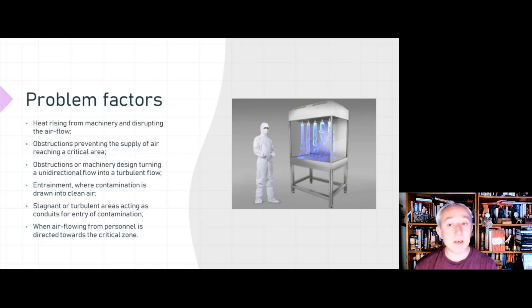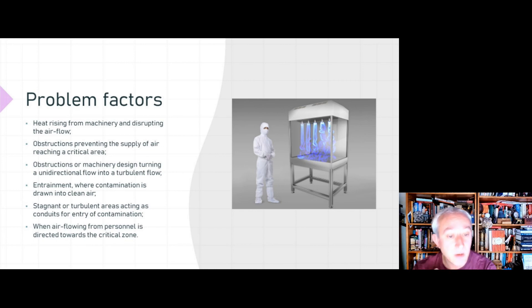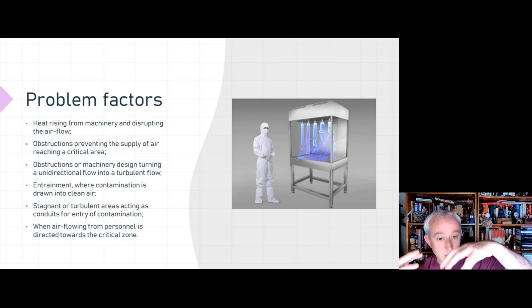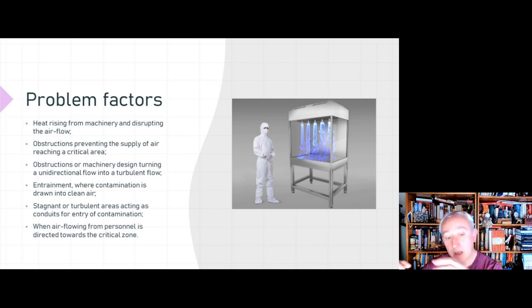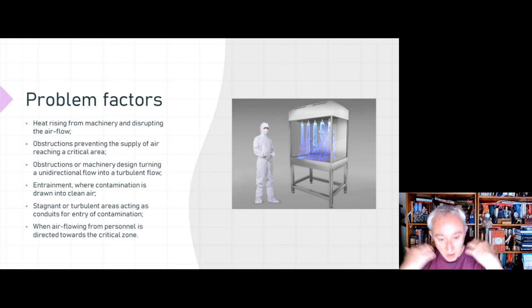Problems can arise when conducting airflow studies. Heat rising from machinery can disrupt airflow — opening a hot autoclave, for example, can cause significant disturbance. Obstructions can prevent air supply from reaching critical areas, or turn unidirectional flow into turbulent flow. Entrainment can bring contamination into the clean air zone, and stagnant or turbulent areas can act as conduits for contamination entry. When a person intervenes in the critical zone, we don't want to see air rolling off the person and being directed into the critical zone — the air should still flow over the person and out.